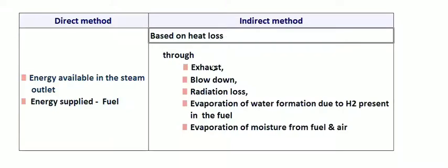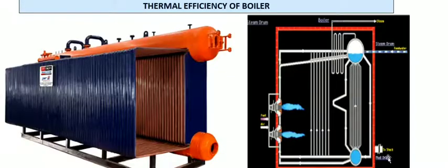Normally you see heat losses, definitely the fuel we are spending here, air we are supplying in that. Major losses will be in the air exiting from the boiler, the exhaust flue gas will carry the heat content, because we are not able to utilize all the heat energy transfer. We want to maintain the stack temperature, the exhaust gas temperature. Why? Because the flue gas has sulfur content, so definitely it will reach the dew point and get condensed.